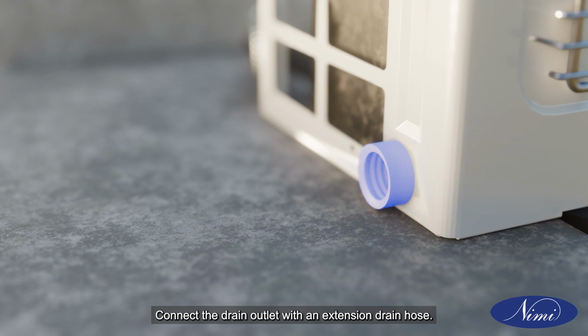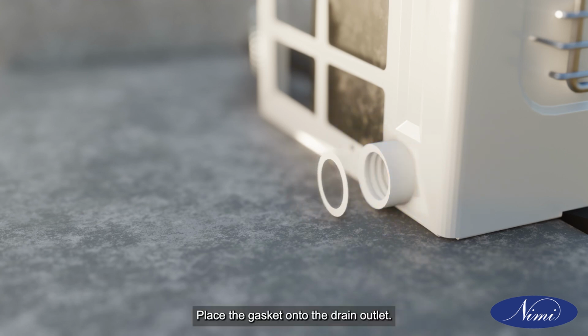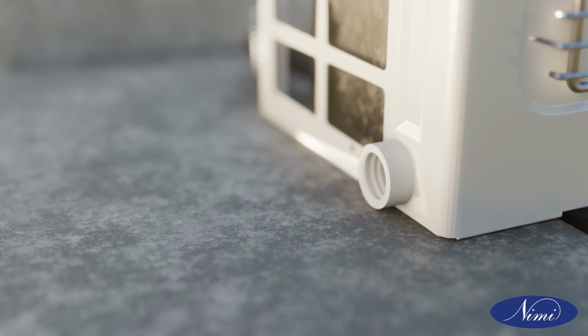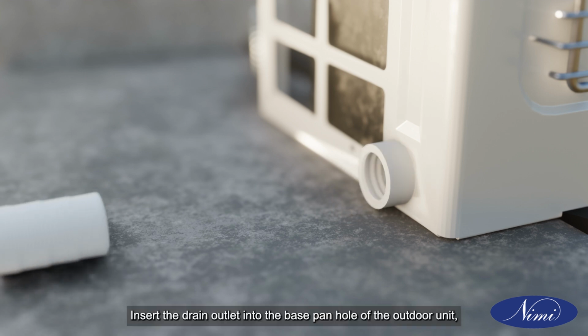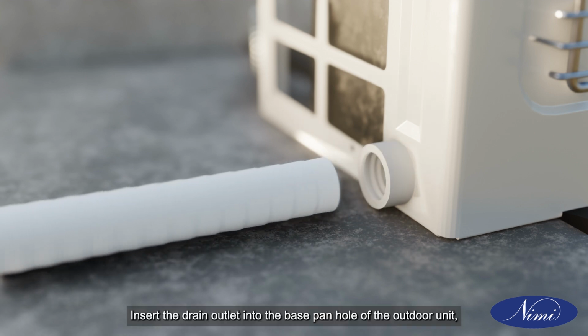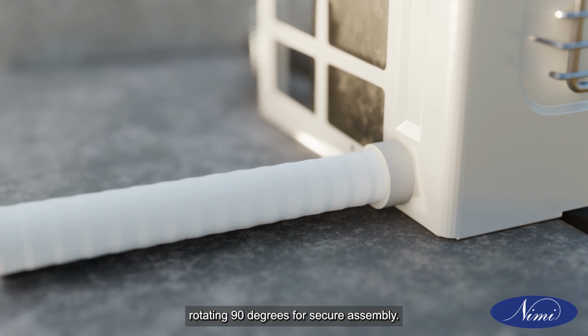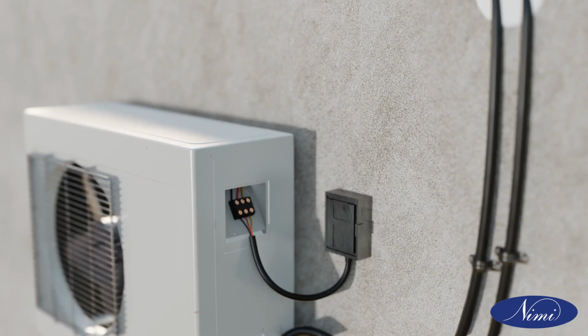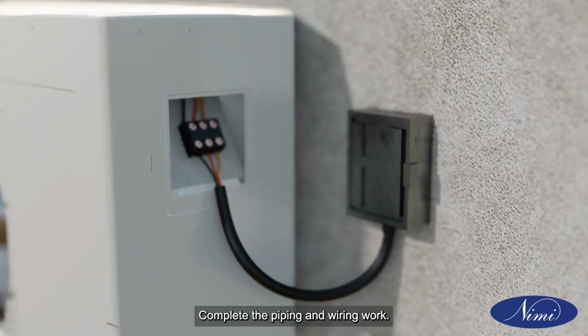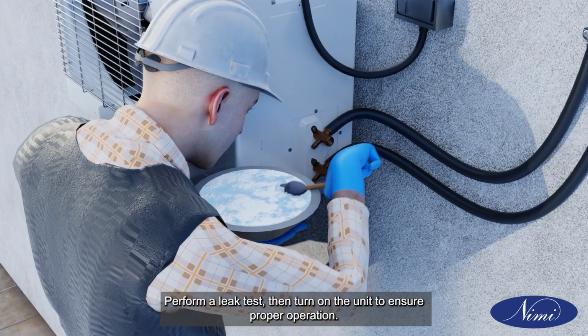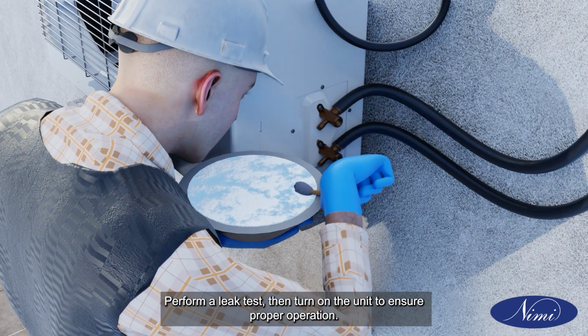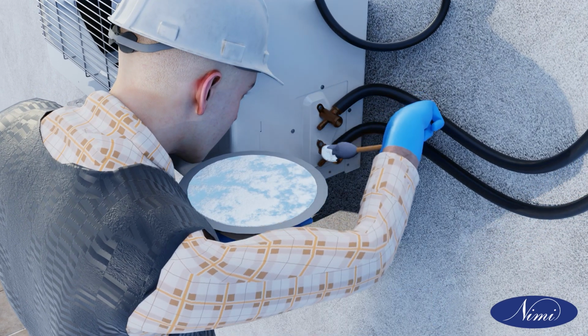Installation of the drain pipe for the outdoor unit. Connect the drain outlet with an extension drain hose. Place the gasket onto the drain outlet. Insert the drain outlet into the base pan hole of the outdoor unit, rotating 90 degrees for secure assembly. Complete the piping and wiring work. Perform a leak test, then turn on the unit to ensure proper operation.